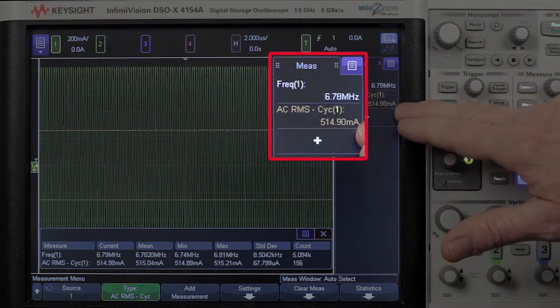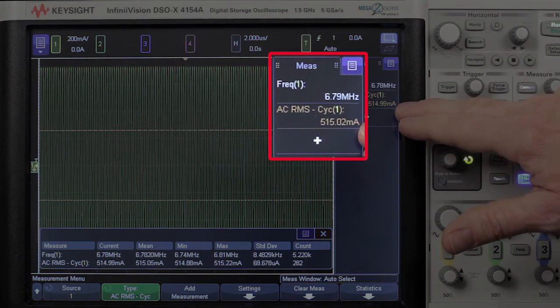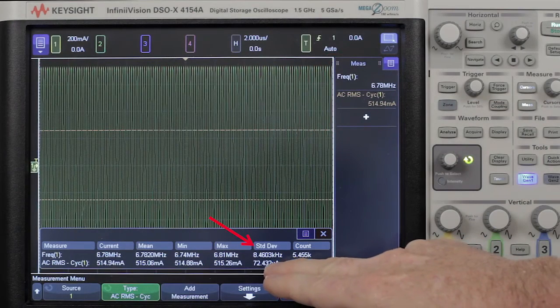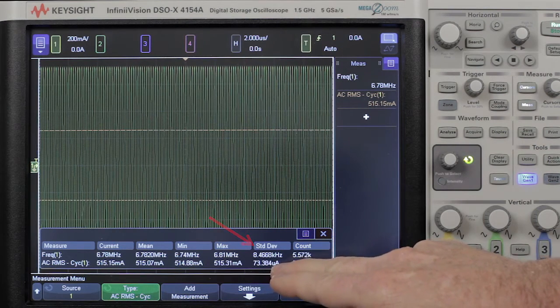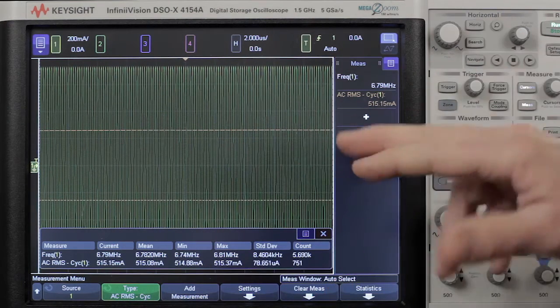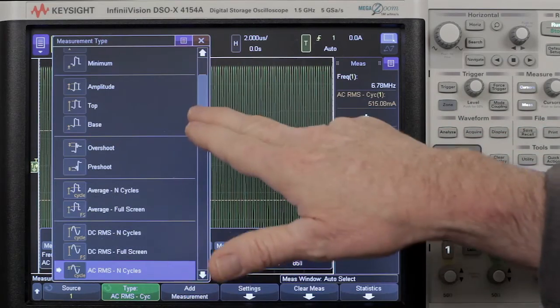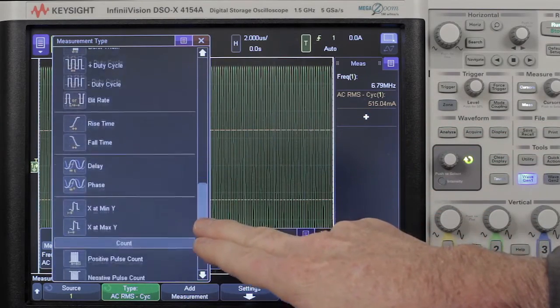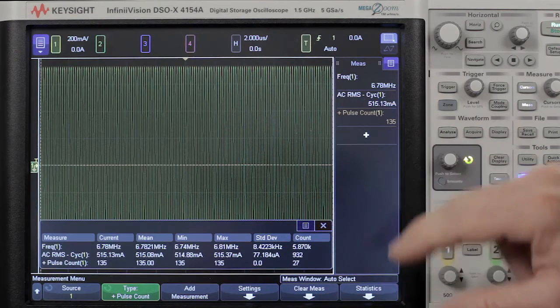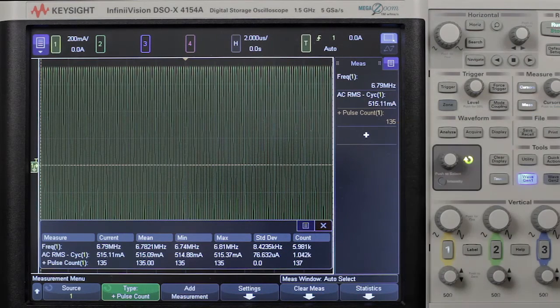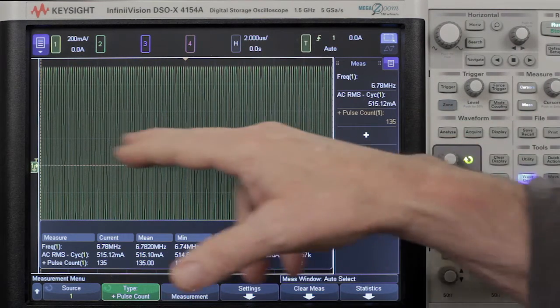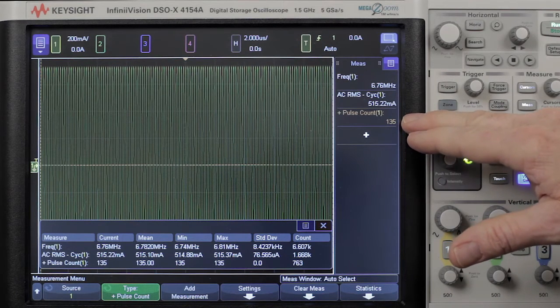And there we're measuring about 515 milliamps with about 100 microamps resolution. You can see the standard deviation here is about 72 microamps. We can add a measurement just for curiosity to find out the number of cycles the measurement is performed across. The number of cycles is about 135. The conformance specification talks about making the measurement based on 100 measurements. You could average 100 times, but it's better just to get over 100 cycles on screen, and there's your measurement.